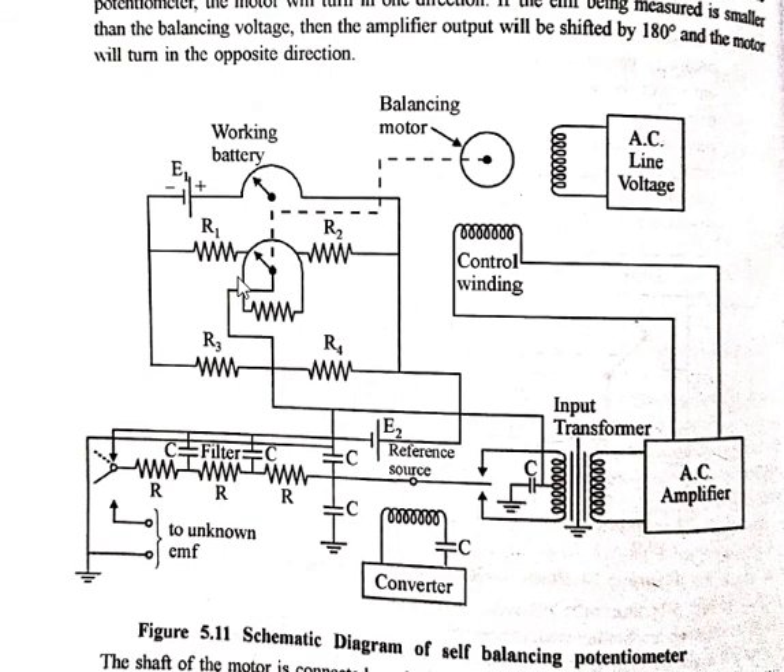The shaft of the motor is mechanically coupled to the slide wire contact in such a way that the rotation of the motor decreases the unbalance of the potentiometer circuit. Whenever there is a decrement in the unbalance of the potentiometer, the motor rotation also decreases — indicating that the unbalance of the potentiometer is being resolved.